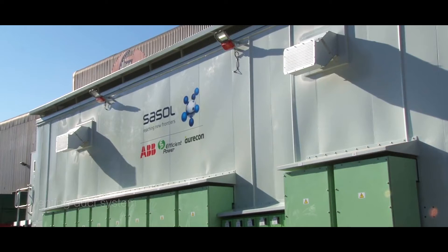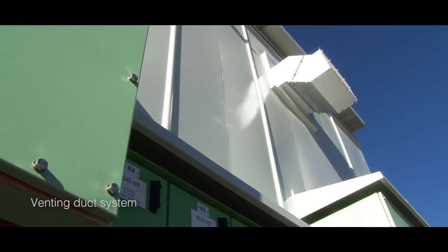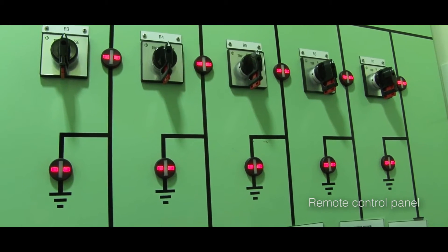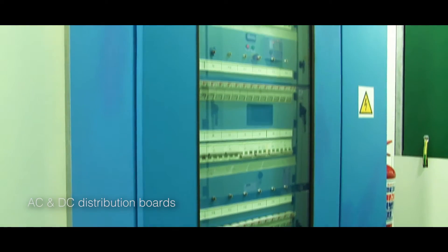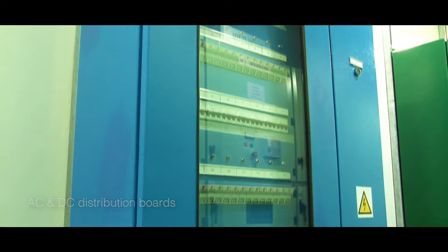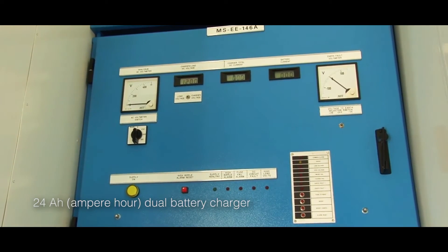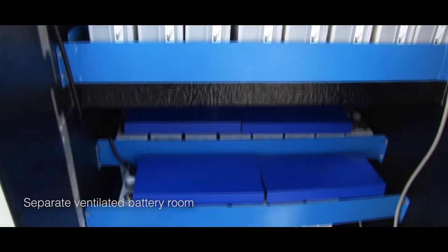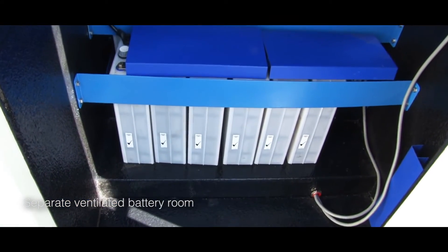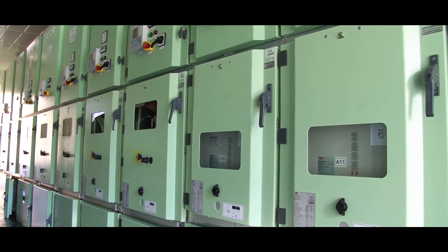The e-house is equipped with a venting duct system to release pressure and heat. A remote control panel allows safe switching from a separate room. The auxiliary power supply consists of AC and DC distribution boards, an interposing relay panel, and a 24Ah dual battery charger, with batteries stocked in a separate ventilated room. The alarm annunciator panel informs operators of dangerous conditions, following the IEC 61850 protocol.